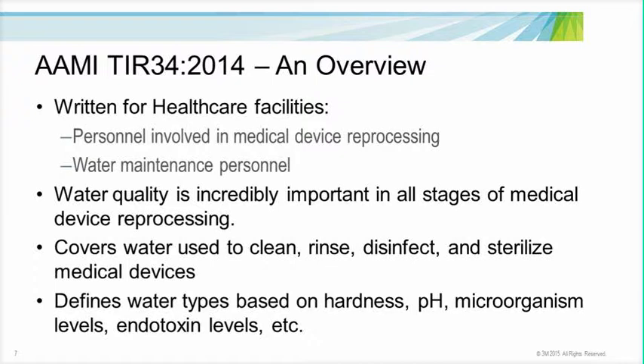The quality of water for medical device reprocessing is important at all stages of reprocessing and more important during specific stages. This technical informational report covers the quality of water that is to be used during the procedures during the clean, rinse, disinfect, and sterilization of medical devices during the reprocessing steps. It also defines specific water types based on hardness, pH, microorganism levels, bacterial endotoxin levels, and so on.